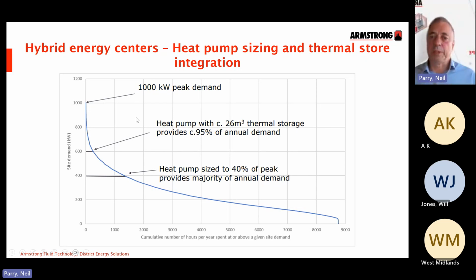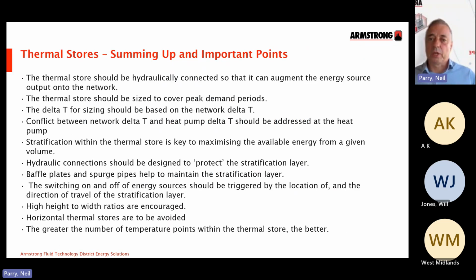So summing up, I think I've probably talked through most of these as we've gone through, but you can see some of the critical aspects, and really stratification in that thermal store, and not allowing flow to go through the thermal store, is critical. And we need to think about having a high height to width ratio, so we can see a very definite stratification layer, see what it's doing, and you can control from it much more accurately. I hate to see thermal stores when they're tipped on their side, because there may be height restrictions in the plant room.